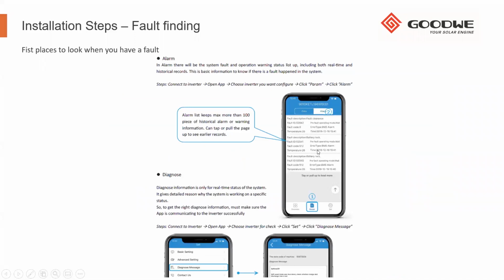Like I said previously, some alarms may not show on the SEMS portal as well. So if you go to site, you connect with your PV Master, you go to the param page, you'll see there's alarms. The inverter itself stores up to 100 alarms. So it's a good place to come and look to see what alarms your inverter has been giving. This will also give us a good indication. You can scroll through the alarms to see more of the alarms.